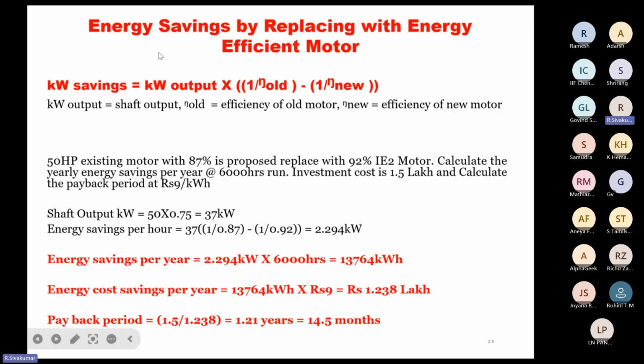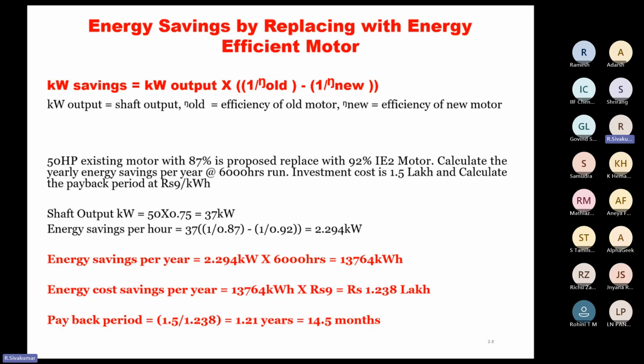So this is a simple calculation of energy saving by replacing with an energy efficient motor. This is the formula: kW output times (1 divided by old efficiency minus 1 divided by new efficiency). For this simple example, a 50 HP, that is a 37 kilowatt motor, is replaced with a 92% IE2 energy efficiency motor. The old efficiency is 87%. Consider the motor is running for 6,000 hours in a year.